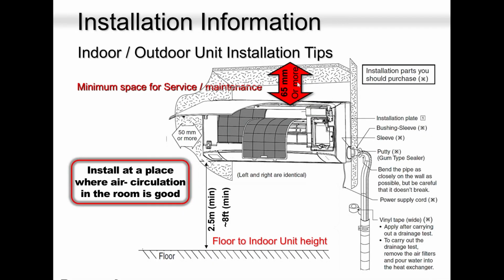Always remember to keep space at the top. Keep enough room at the top so that air doesn't get trapped there. The guy is calling me in the morning or in the night and telling me, "Paul, last night I left the system at 21 degrees, 22 degrees, and it never came on." That's because hot air got trapped here in heat mode, and it put that sensor to sleep. And that sensor told the compressor outside, "I'm happy." Meanwhile, the guys are freezing downstairs. The guys are super freezing because hot air got trapped. Always keep enough room, guys. Keep enough room so there is enough circulation of air, cold and hot, supply and return.